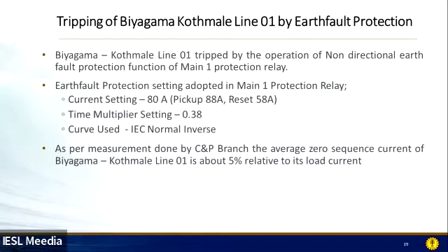As per measurements done by the control and protection branch, the average zero sequence current of the Biyagama-Kothmale line is about 5% relative to its load current. Before this total failure, we had not measured this permanent zero sequence current, and we were unaware of this high unbalanced current in the line.